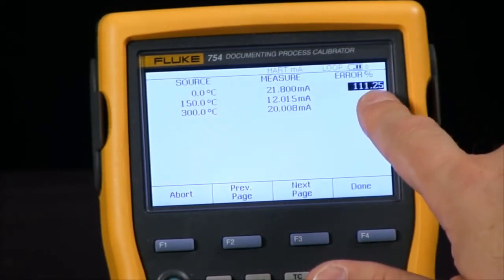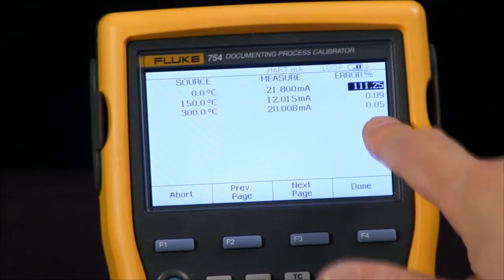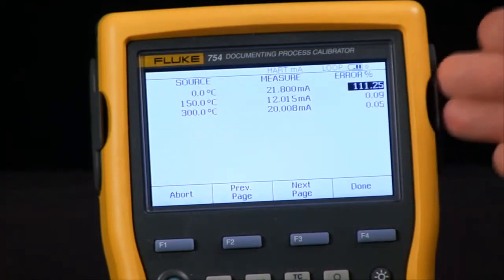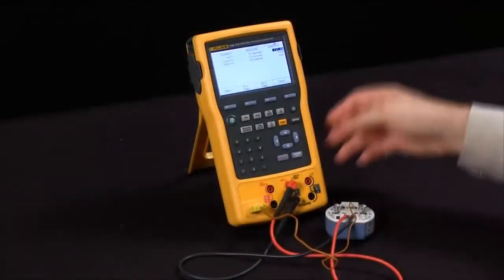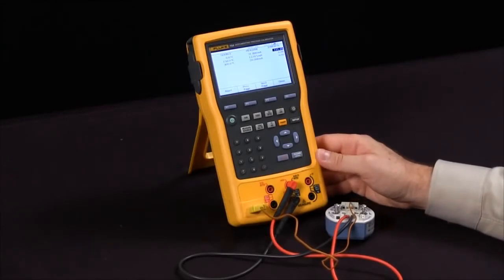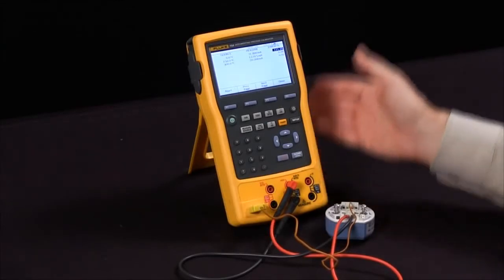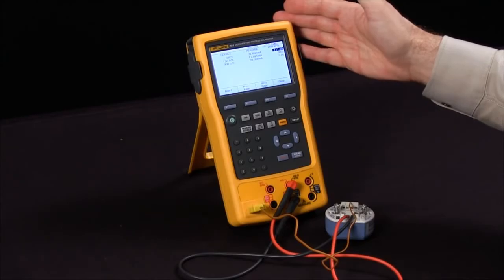I'm out of tolerance with a negative video on the first one, and the last two are in tolerance, so those are in positive video. So this is how you communicate with a HART device and perform a calibration using the Fluke 754 documenting process calibrator.